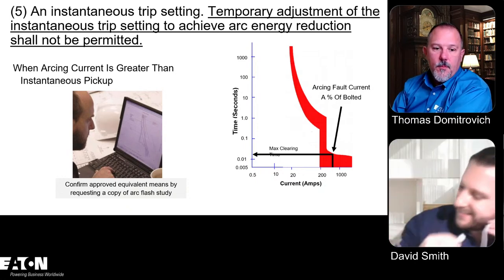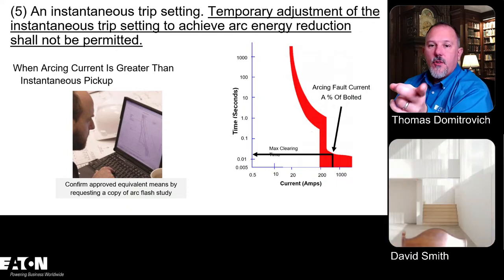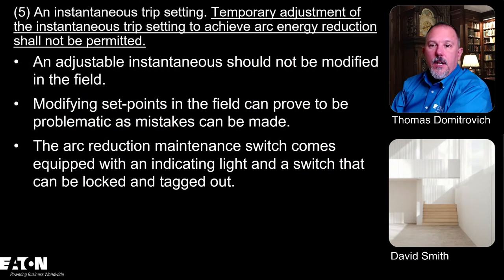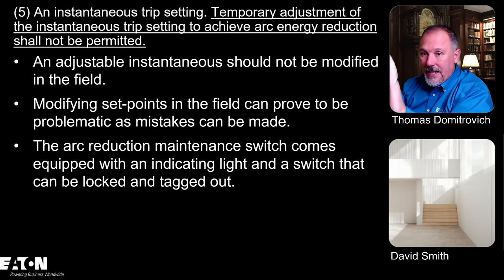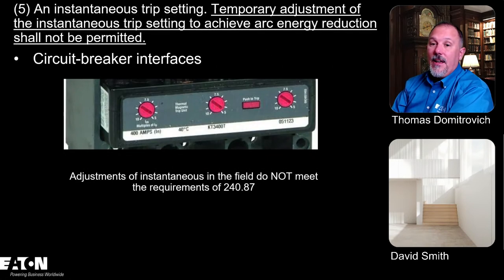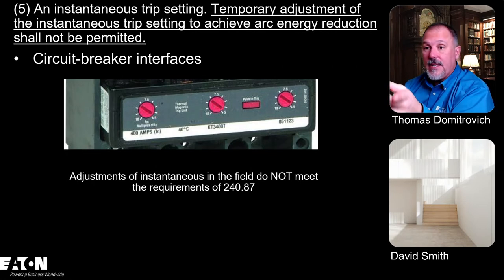So arcing current's greater than instantaneous pickup, and that's option 5. That's the temporary adjustment. And again, don't modify the instantaneous in the field. The reason is that all of these trip units will look different. Some, like in this case, have all three dials controlling the same instantaneous. You have to change all three dials, one for each pole.